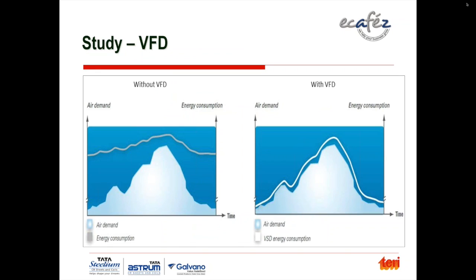Now I will move on to the application of a variable speed drive, in a compressor. Essentially, the air demand in the plant varies, with peak demand and lower demand. Without a VFD, energy consumption decreases only by a small amount. By using a VFD, you can reduce the no-load power consumption and make the energy curve follow the compressed air curve very closely. If the compressor is loaded higher, you use higher energy; when underloaded, you use a lower amount of energy.